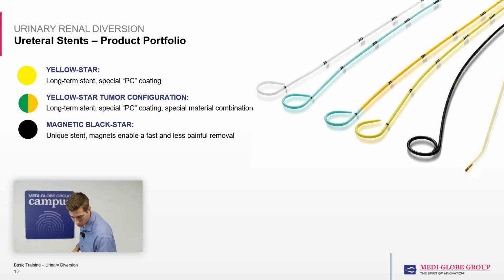Last but not least, we're talking here about our so-called magnetic Black Star, the black one. This is a very unique solution, the only solution that enables the withdrawal of the stent with a magnet. That means here there's no cystoscope needed for the insertion and the removal of the stent. And this ensures a better cost-efficient procedure because there's no cystoscope needed. And on the other hand side, it's more convenient and less painful for the patient to remove the stent.